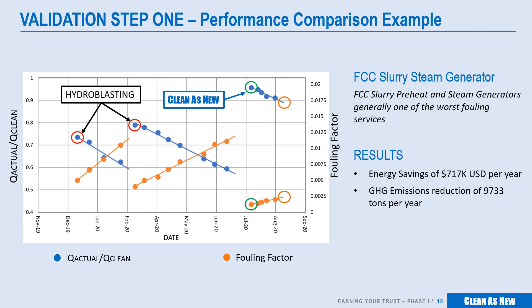There's another really important feature evident in these results: the slower initial fouling velocity observed after a more thorough cleaning. The previous interval between cleanings was approximately 2 to 3.5 months. If we bend the initial fouling curve to match the post-induction behavior seen in previous intervals, and the same cleaning performance trigger is used, we see that the interval can be extended to more than double the previous average, providing not only runtime, energy and performance improvements, but cutting required maintenance by half.